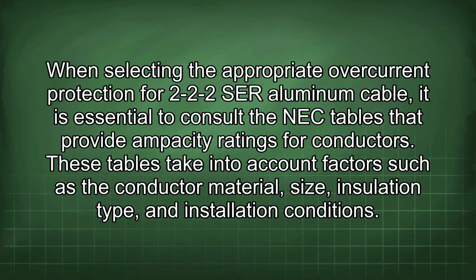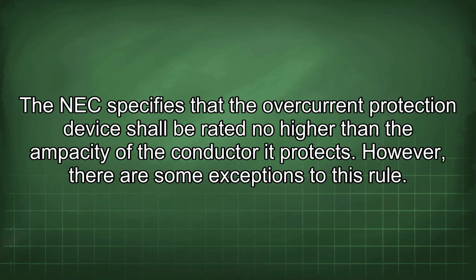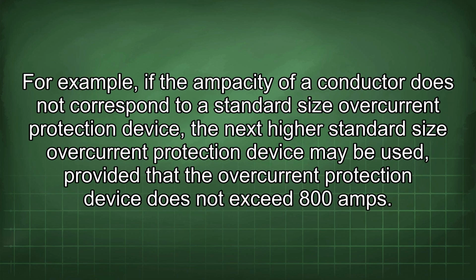These tables take into account factors such as the conductor material, size, insulation type, and installation conditions. The NEC specifies that the overcurrent protection device shall be rated no higher than the ampacity of the conductor it protects. However, there are some exceptions to this rule. For example, if the ampacity of a conductor does not correspond to a standard size overcurrent protection device, the next higher standard size overcurrent protection device may be used, provided that the overcurrent protection device does not exceed 800 amps.